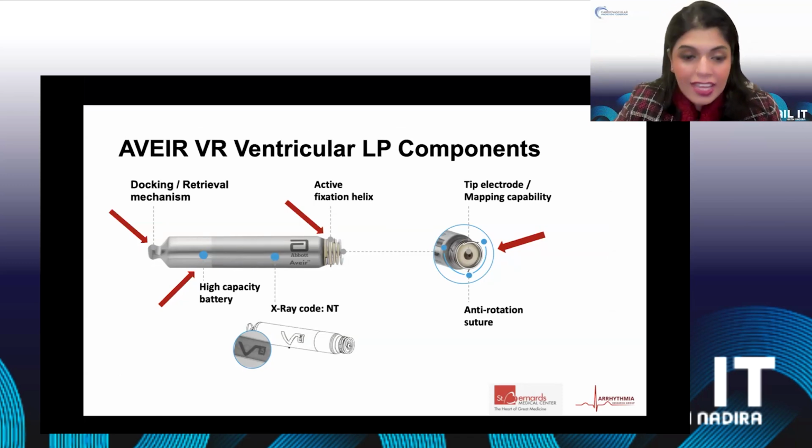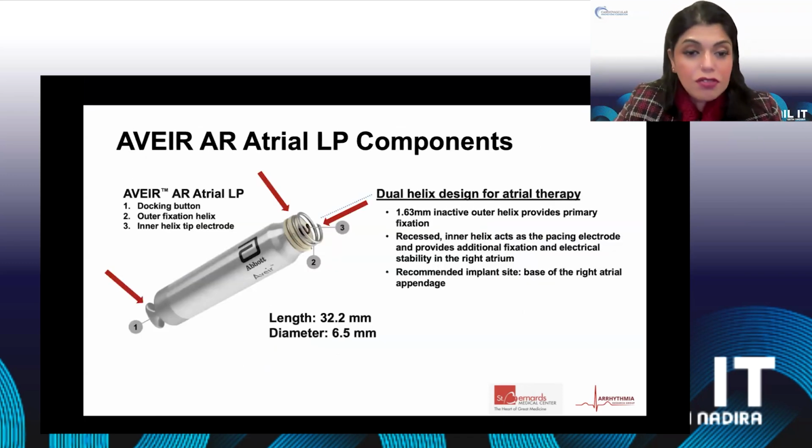So can leadless pacemakers affect the tricuspid valve? There was a question in Q&A. If you put this device too close to the valve, yes, of course, it can affect the tricuspid valve.